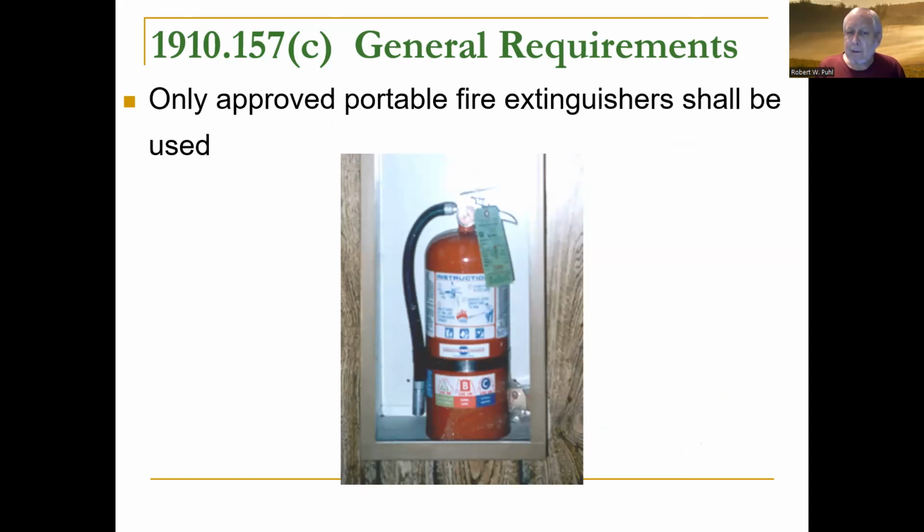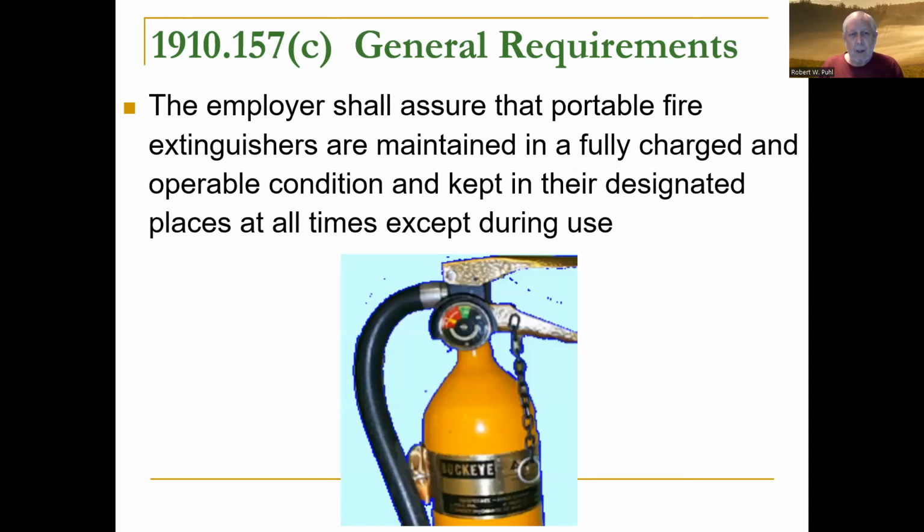You're probably not. But if you have them, you're going to have somebody come in every year and do a maintenance check on them. There are stampings on all these things that look like hieroglyphics to me, but these people seem to know what they mean when they look at it. I guess you could figure it out if you look at it. They'll be able to tell you when they're due for hydrostatic testing and all that stuff. And chances are, if you buy a fire extinguisher, it's going to be approved by somebody.